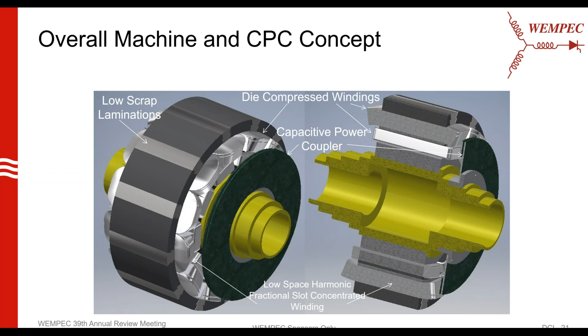So this is the rotor of the machine that we had available to experiment with. This is a 30 kilowatt continuous, 55 kilowatt peak, 4,000 RPM base speed machine. It requires 4 amps DC field current, and with a field resistance of 42 ohms, that comes out to about 675 watts of power needed to drive those coils on the rotor.